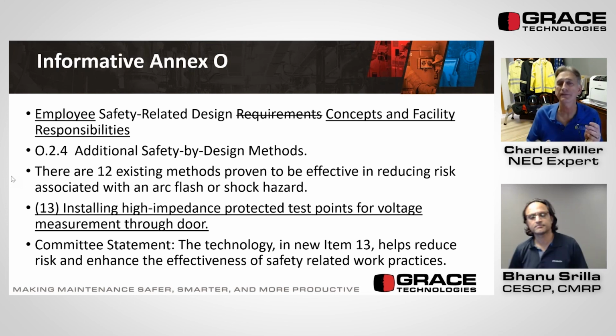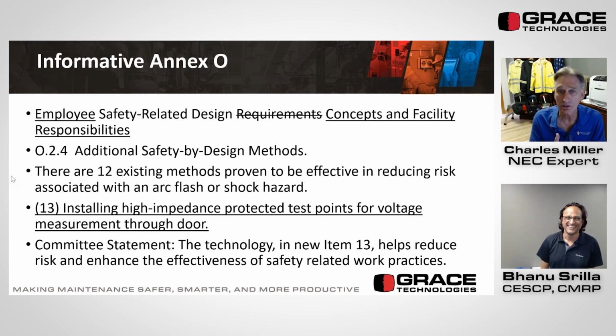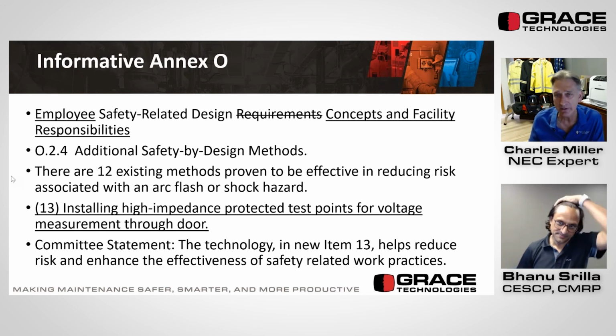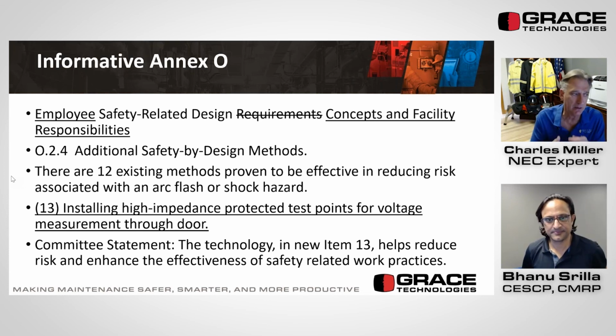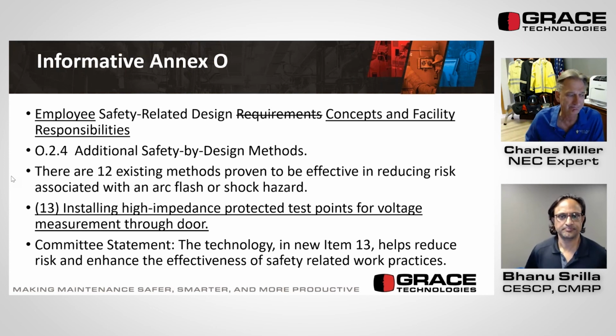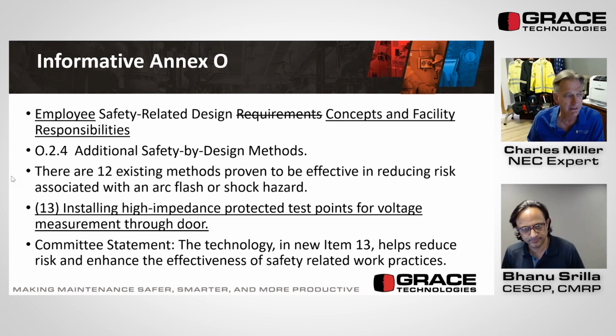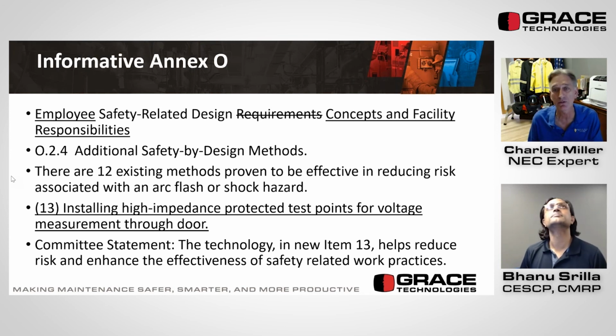All right, so what if everything was installed correctly, it has the plaque on the equipment, and then the utility company changed the transformer? Yeah, that could change something. So this could just go on forever. But you're also not going to have, on a regular disconnect switch or a regular panel board load center, all these plaques showing the available fault current and what the equipment is rated for.